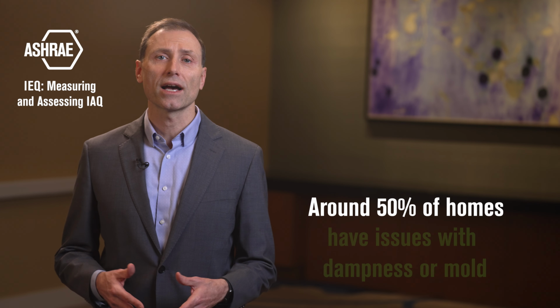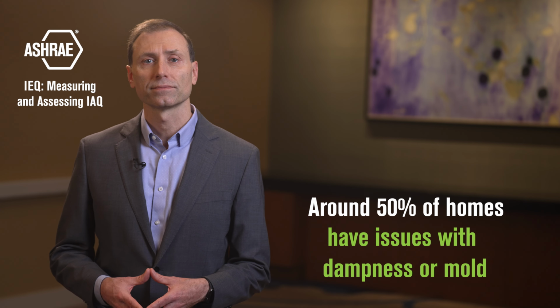If I were to transport myself into your room right now to conduct an indoor environmental assessment, I would start with asking some questions and performing a thorough visual inspection. I'd want to know about any past issues and learn about patterns to odors or symptoms. I'd also want to inspect the space for signs of problems such as water stains, mold growth, and chemical odors. Large studies have found that around 50% of homes have issues with dampness or mold.